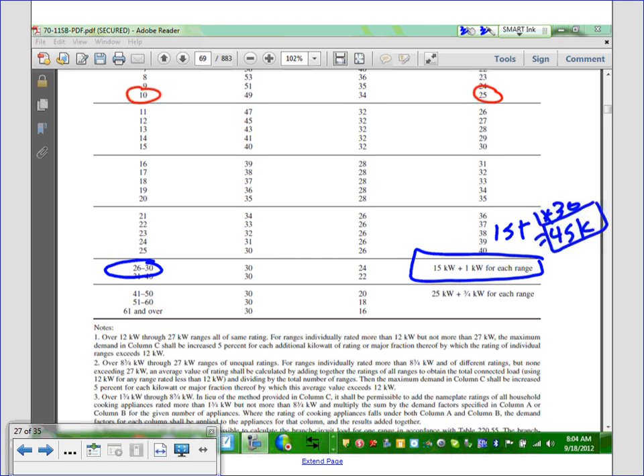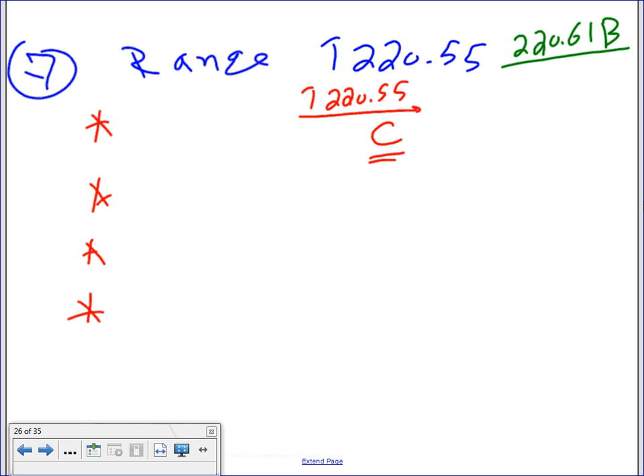Then you up it 5% for every kW more than 12. That's how we do it. So from the get-go, your 10 give you 25. Everybody knows why the 10 gave you 25, because they're all under column C. So let's go back and do the math on that one. I have 19 kW. That's definitely under C. A and B shall not be used, so they'll give you 25 kW from the get-go.